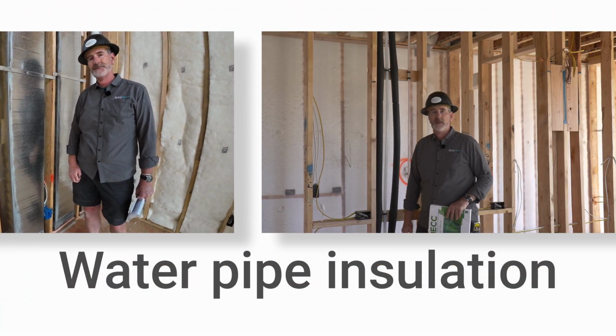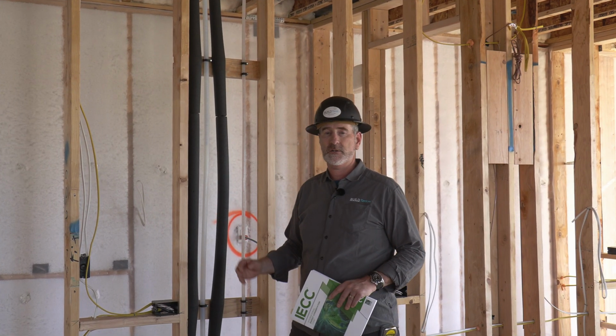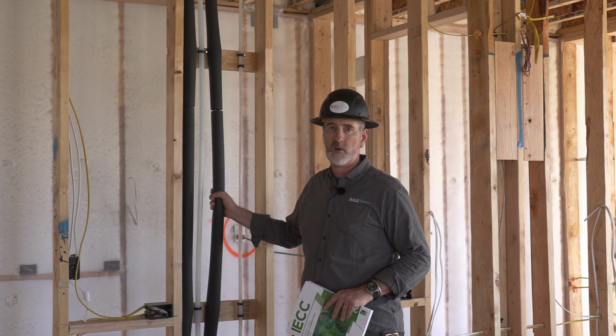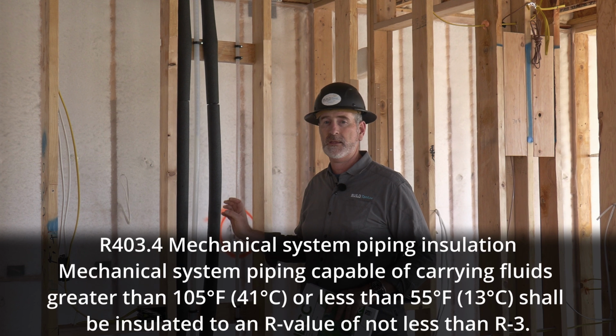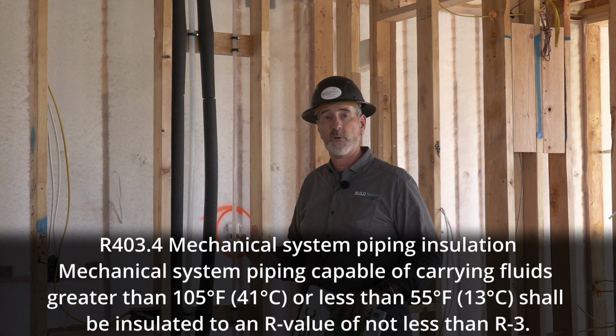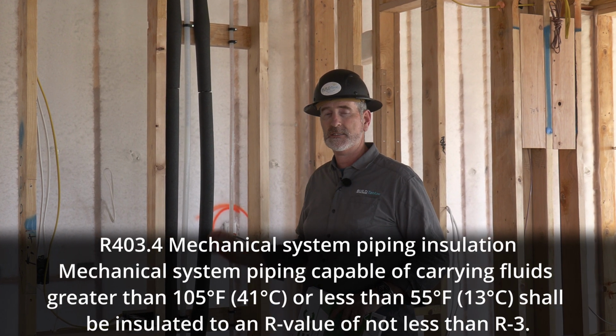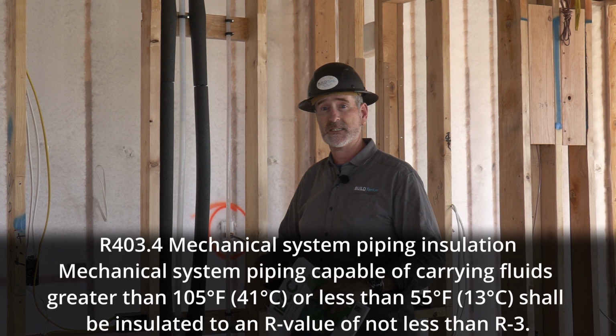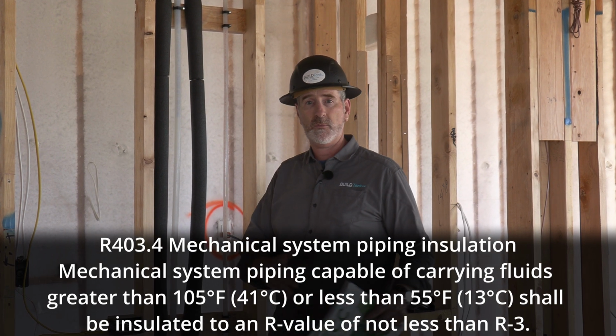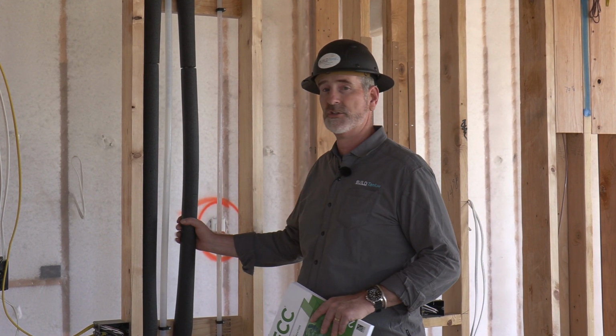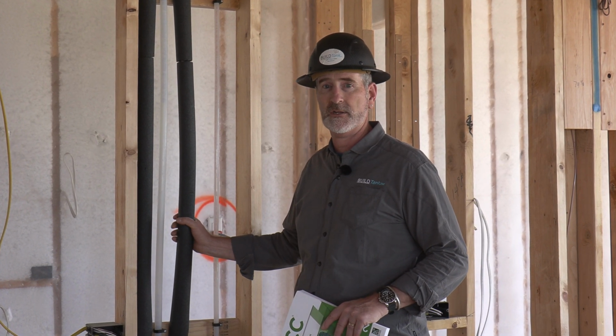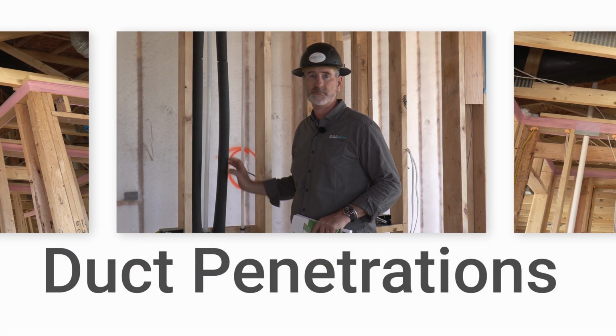Relatively new to the energy code is a requirement to insulate our hot water lines. And if you have a hot water line that is a 3/4 inch line or bigger, it needs to be insulated, even if it's inside the conditioned space, from the water heater to whatever fixture it's going to. So we should be seeing R3 insulation on all of those 3/4 inch lines that are carrying hot water.